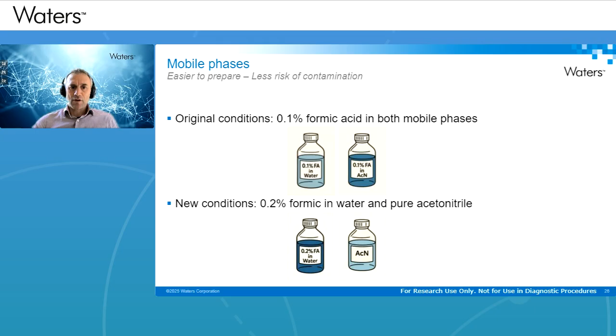A remark that we sometimes received from our customers was that upon immediate injection of the derivatized sample, some amino acids, mostly the basic ones like arginine, showed peak fronting or even peak splitting. And when the same sample was injected the day after, the peak shape was good. Now, our theory is that the 20% acetonitrile that is in the vial as a result of the derivatization may have played a role here. And as soon as some of the acetonitrile evaporates in the vial, this detrimental effect is no longer observed. So what we did was a simple dilution of the derivatized sample with water, and this actually solved the issue.